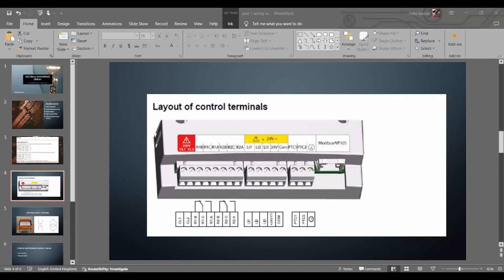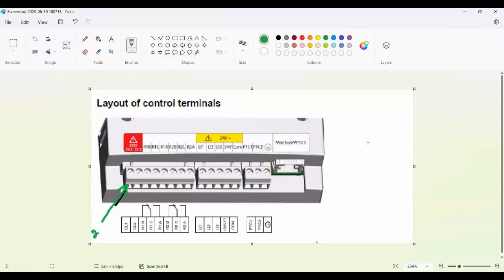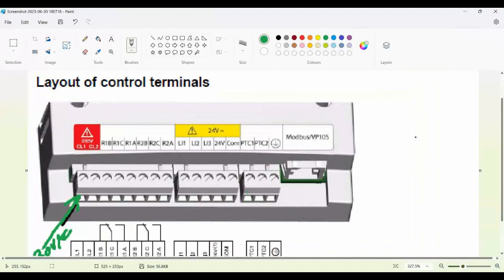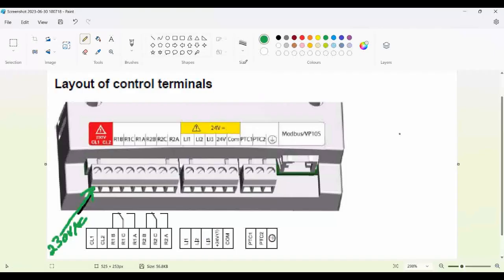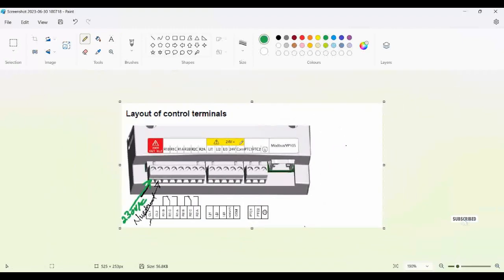The control terminals are equipped with one-way plug-in connectors with a maximum connection capacity of 2.5 mm², 12 AWG, and a maximum tightening torque of 0.5 Nm, 4.5 lb-in. CL1 and CL2 are the ATS22 control power supply terminals, and we will incorporate a step-down control transformer rated at 380/220 VAC. The one-way connectors also hold a set of relays for controls, each with a maximum switching capability of 5A at 250 VAC or 30 VDC on a resistive load, power factor equals 1, 2A at 250 VAC or 30 VDC on an inductive load, power factor equals 0.4, and a minimal commutation capability of 100 mA at 12 VDC. It is mandatory that one of the relays, R1 or R2, must be set to trip.